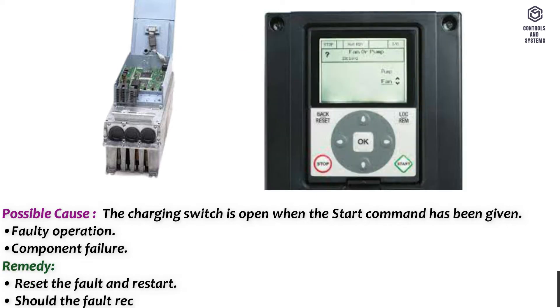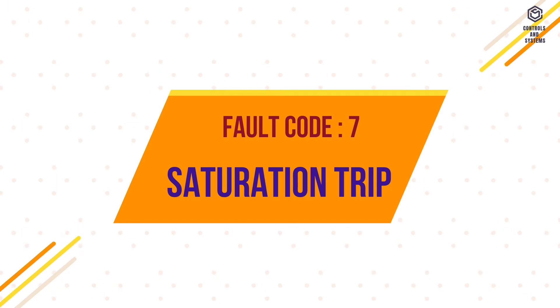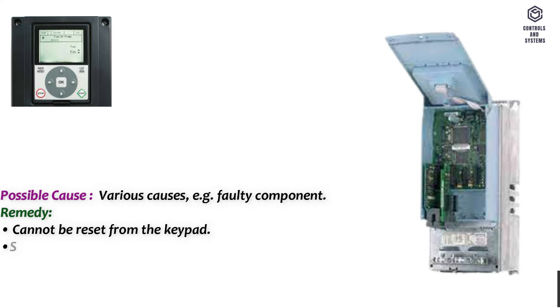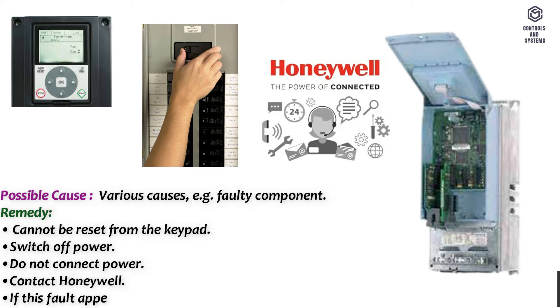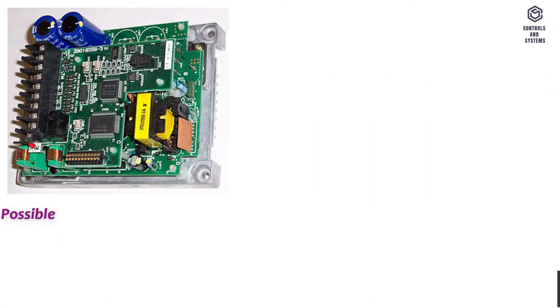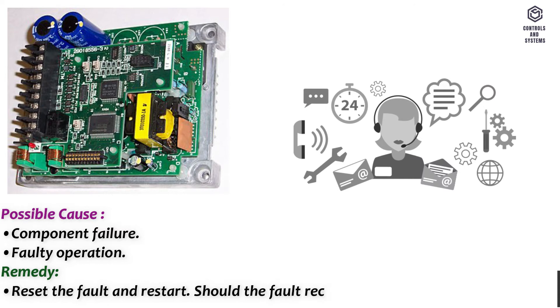Fault code 7 – Saturation trip. Possible cause: various causes, for example a faulty component. Remedy: cannot be reset from the keypad; switch off power, do not reconnect power, and contact Honeywell. If this fault appears simultaneously with fault 1, check motor cables and motor. Fault code 8 – System fault. Possible cause: component failure or faulty operation. Remedy: reset the fault and restart; should the fault recur, contact technical support.